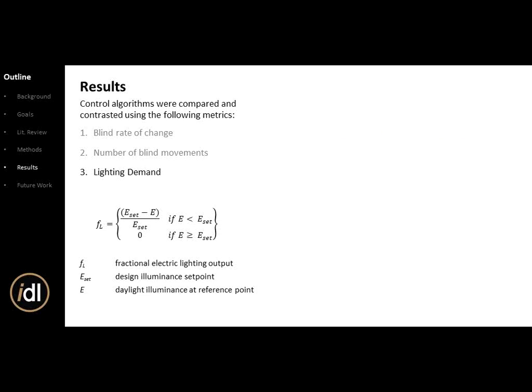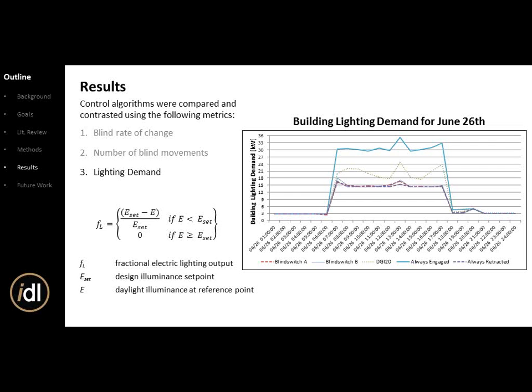Lighting demand was the next comparison metric — basically your set point inside minus the actual value, divided by the set point. For June 26th across all five models: always engaged has the highest demand because no daylight comes in, so you're using the most electric lighting. DGI in green is close behind. Blind Switch A, B, and always retracted have very similar lighting demand values.